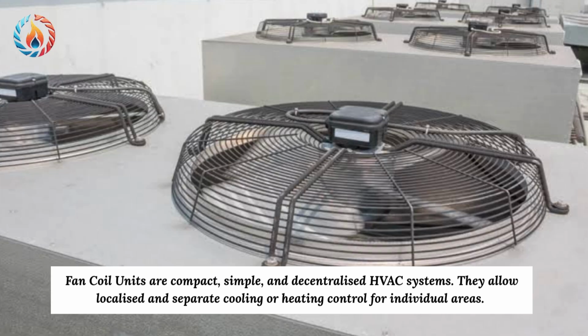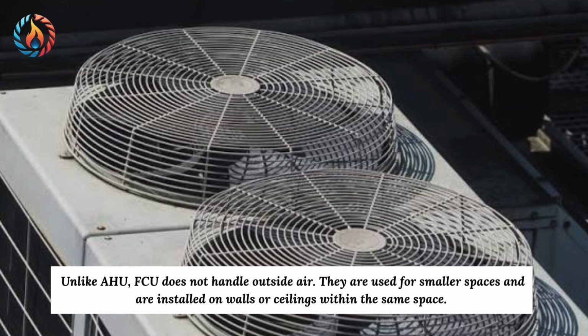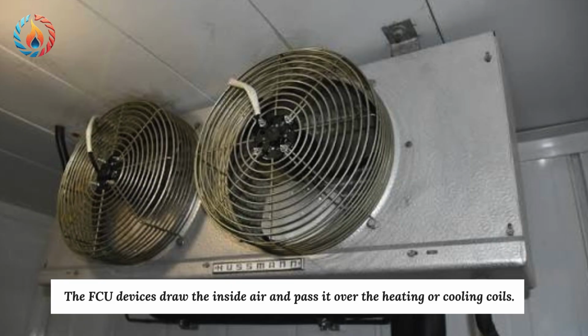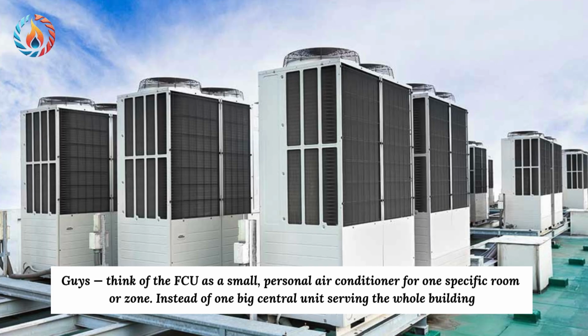Fan coil units are compact, simple, and decentralized HVAC systems. They allow localized and separate cooling or heating control for individual areas. Unlike an AHU, an FCU does not handle outside air. They are used for smaller spaces and are installed on walls or ceilings within the same space. The FCU devices draw the inside air and pass it over the heating or cooling coils. Guys, think of the FCU as a small, personal air conditioner for one specific room or zone.